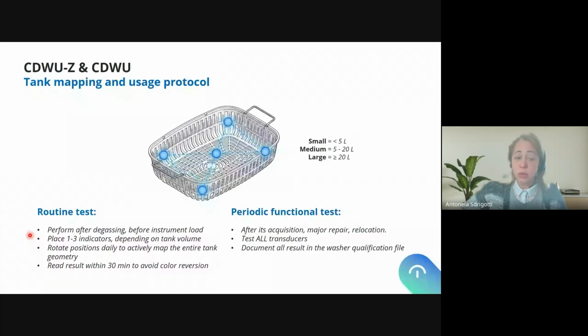We will place 1 to 3 indicators depending on the tank volume. We will rotate positions. Here are just some examples. We have to make sure that the corners are normally the cold spots, due to the configuration, as I have mentioned, in which the waves of energy run through the tank.